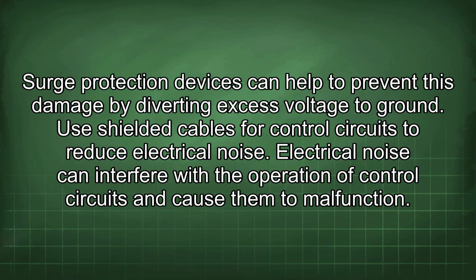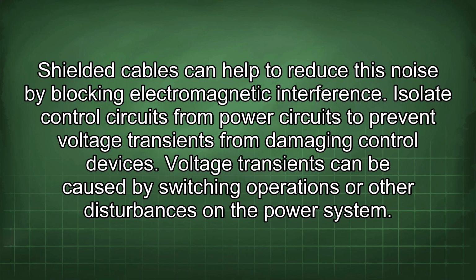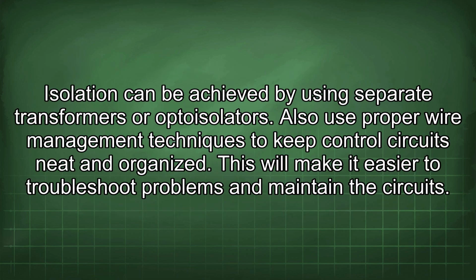Use shielded cables for control circuits to reduce electrical noise. Electrical noise can interfere with the operation of control circuits and cause them to malfunction. Shielded cables can help to reduce this noise by blocking electromagnetic interference. Isolate control circuits from power circuits to prevent voltage transients from damaging control devices. Voltage transients can be caused by switching operations or other disturbances on the power system. Isolation can be achieved by using separate transformers or optoisolators.